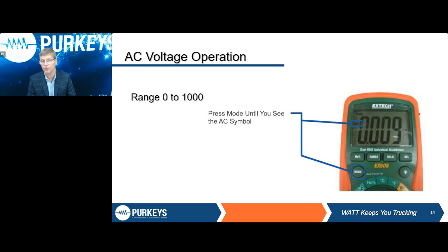of that meter. What I've seen, though, at times people will buy a generic meter or an economical meter, and it may cap out at 400 volts. So as we get into the EV market, or if you're doing any type of industrial maintenance as well, where you're getting into voltages above that, your meter can't read it. And that is definitely not a time you want to stick your hands in somewhere you shouldn't, assuming there's no power there.